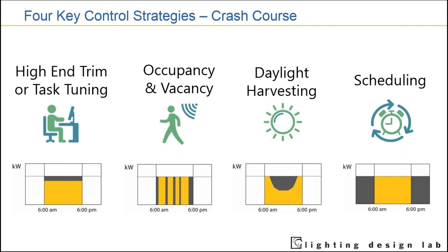Daylight harvesting - hey, if I need to have 30 foot candles on my surface and natural light by the window gets me 80% of the way there, then I'll only need to use 20% of my electric light to get to the right foot candles, evading glare, saving energy. And also scheduling, ensuring that lights are on and off even if there's no one there, be it for safety reasons, egress, if there's an event, automatically. It not just saves energy, but it automates that built environment as facility professionals can leverage lighting control systems. The real power, again, is when all these strategies work together.